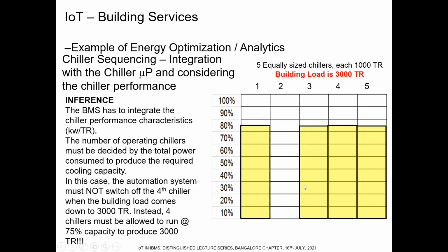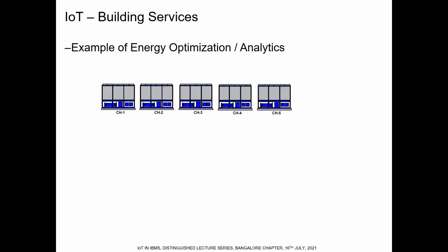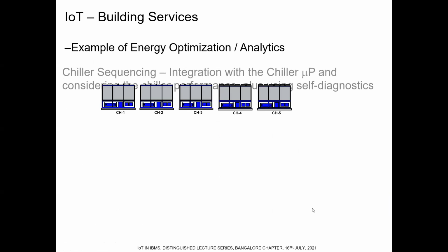Instead of that, the standard BMS would have asked 3 chillers to work at 100% capacity. But now, because interaction has taken place, the BMS would allow the 4 chillers to work at 75% to produce 3000 tons. This is what the second level of sophistication would have taken us to for energy optimization. Now we are not stopping with that. We are doing some analytics. We are also trying to track the chiller. How are we tracking the chiller?